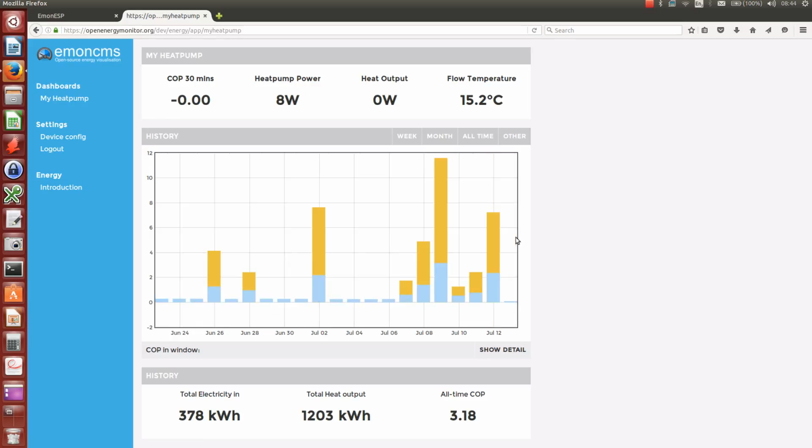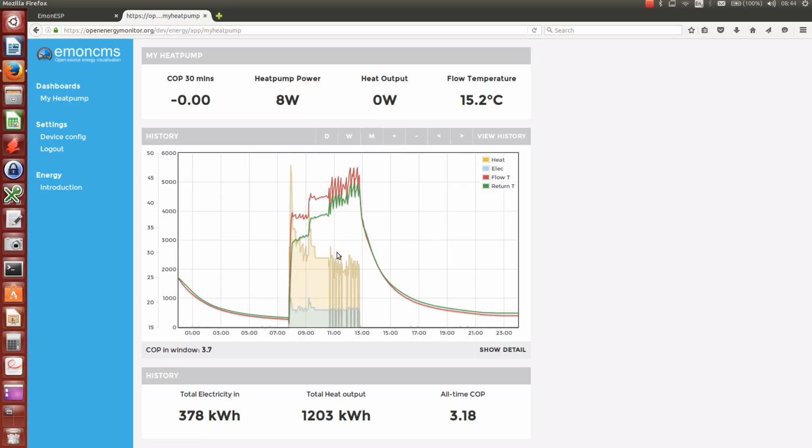But if I just zoom in here and select say 9th of July, I can see the COP on this particular day was 3.7. It consumed 3.2 kilowatt hours of electric, and there was 11.6 kilowatt hours of heat output.